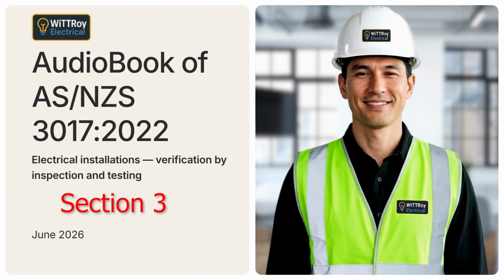For switchboards, the location must be checked. This includes access and egress. In simple terms, people need to be able to get to and away from the switchboard safely. Protective devices must be checked. This includes the selection and setting of adjustable protective devices. The check should consider overcurrent protection, arc fault protection, and discrimination requirements where applicable.